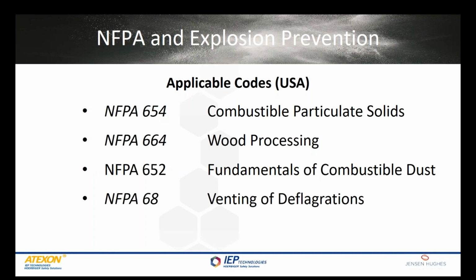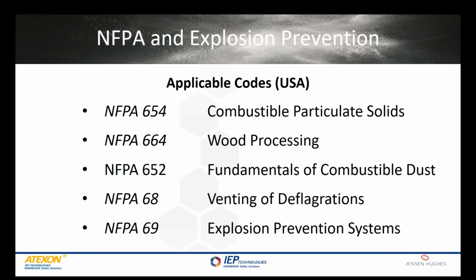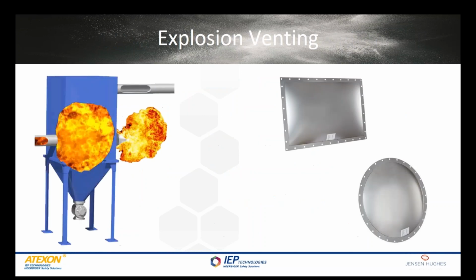Those standards basically tell you where explosion protection should be implemented. The two standards that tell you how those explosion protection measures need to be designed include NFPA 68, which covers deflagration vents, and NFPA 69, which is for explosion prevention systems. By far, the most common explosion protection method is explosion venting. An explosion vent is an opening in a process vessel through which combustion-generated gases can flow and expand. The whole purpose of an explosion vent is to minimize the pressures developed during an explosion to a level below that at which you're going to have rupture or deformation of that vessel.